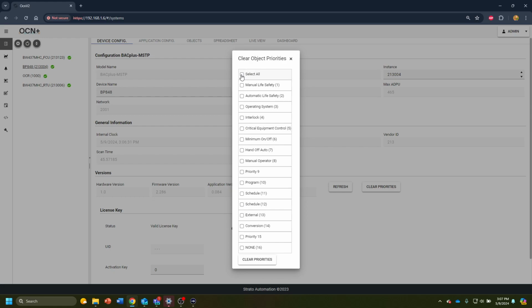If I hit select all, it's going to uncheck them, or I can select all, and it's going to select all of the ones outside of the default program 10 and the minimum on-off time that we are using here to protect the devices, as well as the program level, which is what we normally write at. If I click this, I'm not going to because it's going to take a while, but if I did, it would go and write null to every BACnet object at this priority.